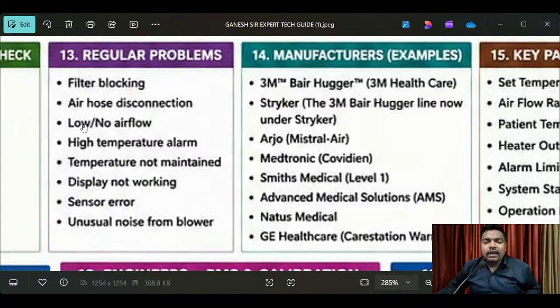Filter blocking, air hose disconnection, low or no airflow, high temperature alarm, temperature not maintained, display not working, sensor error, and unusual noise from the blower. For this purpose, you can do preventive maintenance quarterly, half-yearly and yearly as per the schedule. Preventive maintenance is very important to maintain the reliability of your services. Understand? So these are the regular problems.